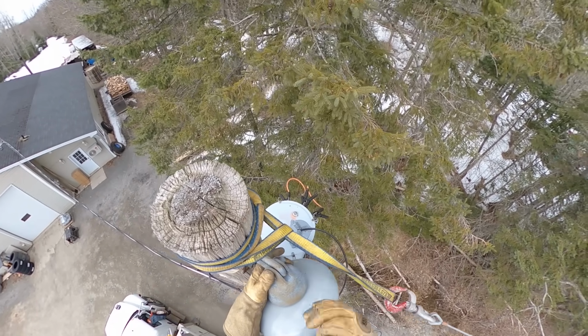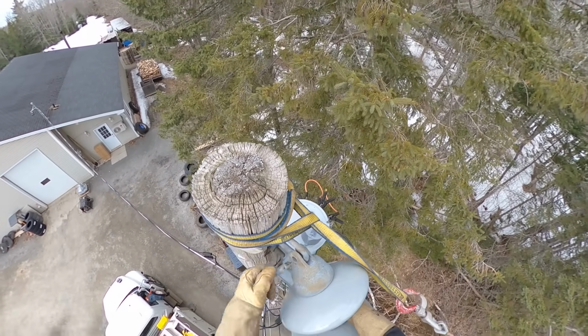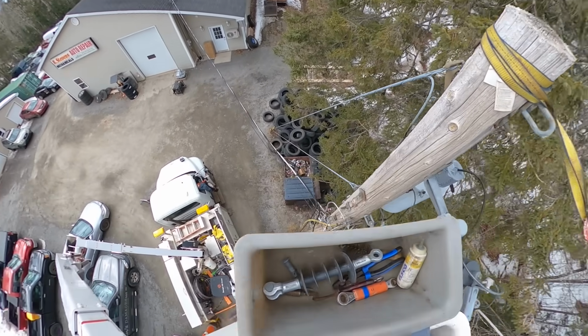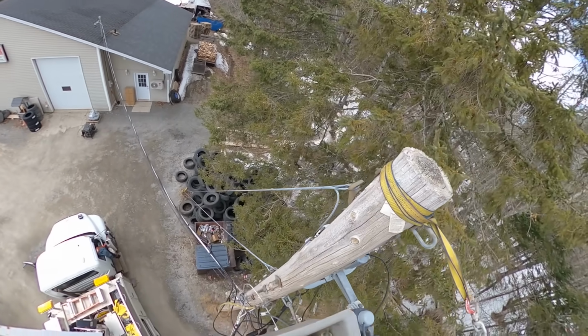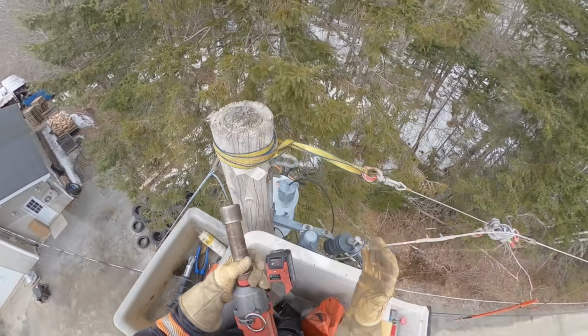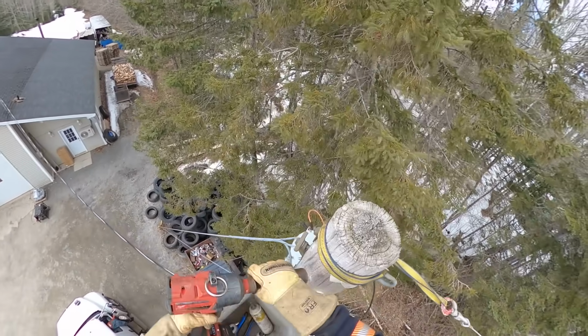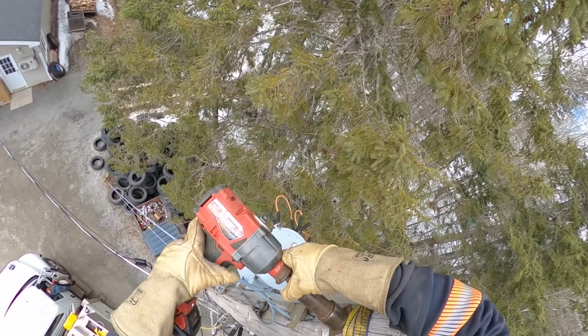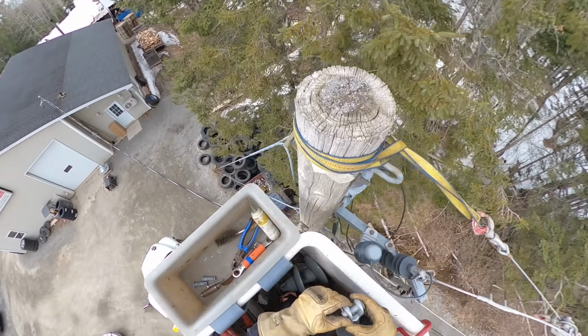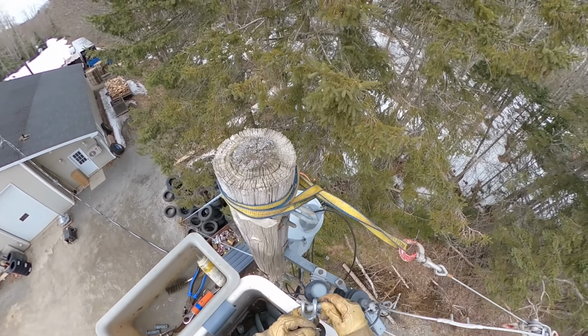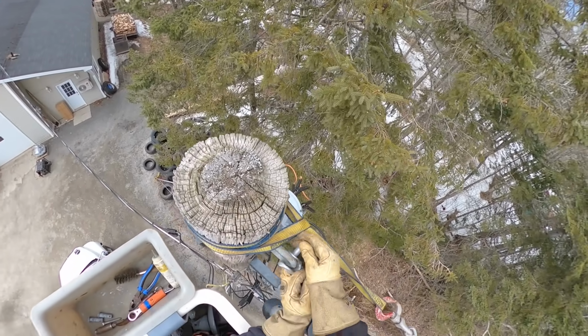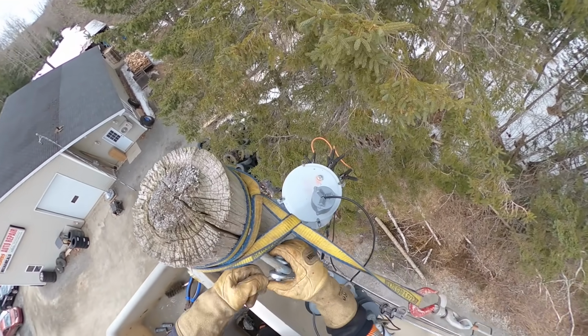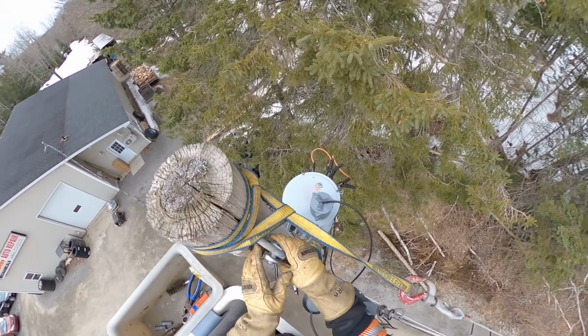So when I pull these out, we do have these special order dead end units. They're good for 15 kV. The reason we use those is for this exact application where you're just replacing old porcelain bells. They're almost the same length, just a tad bit longer. Sometimes you can do a straight swap without resagging the lines.